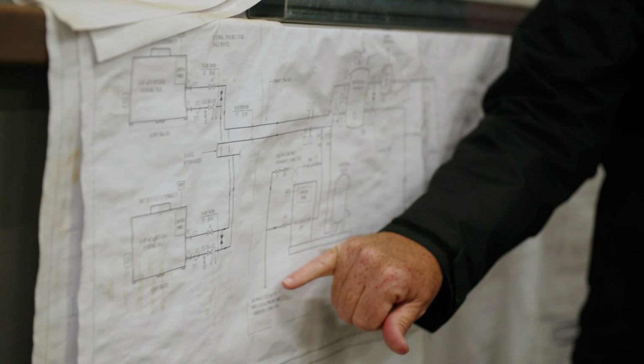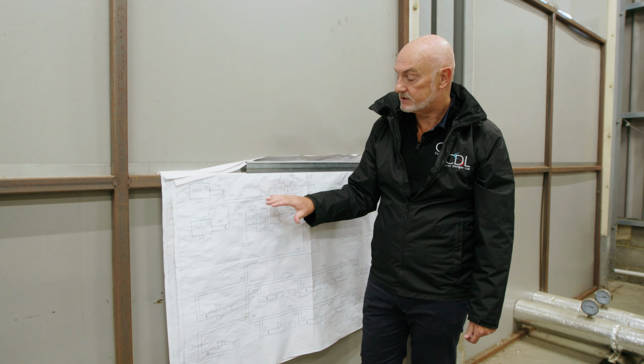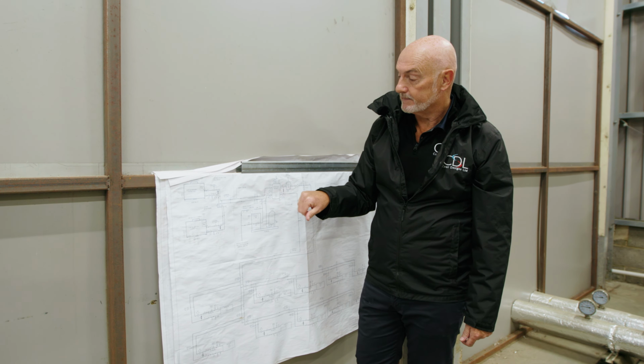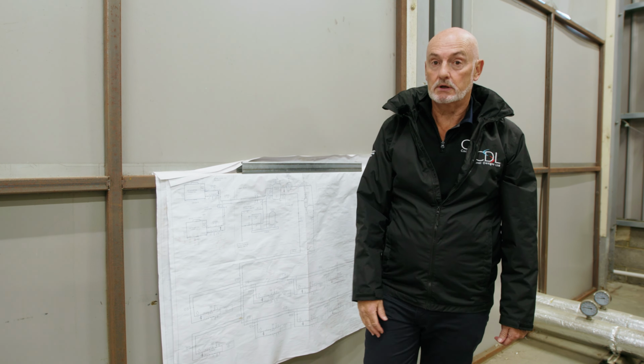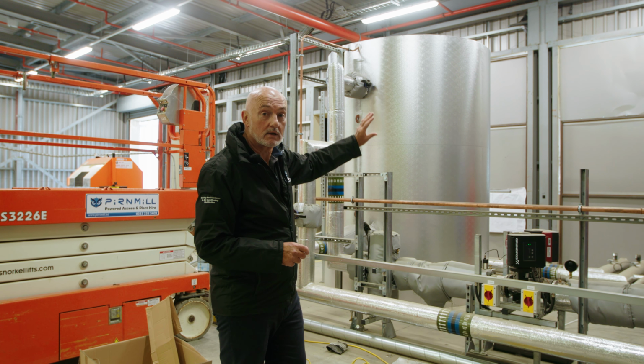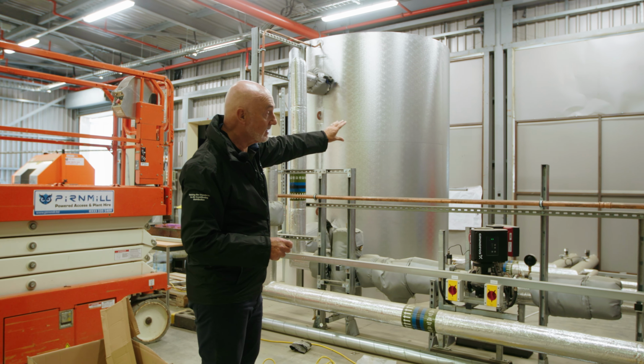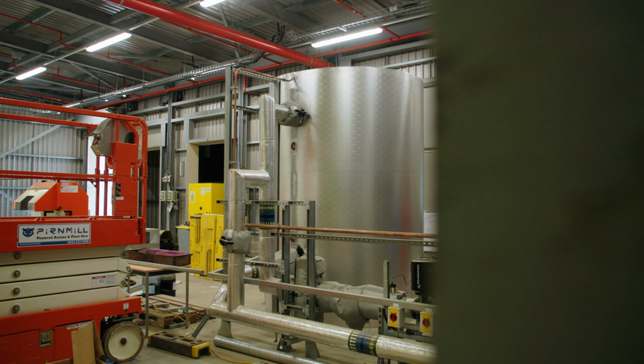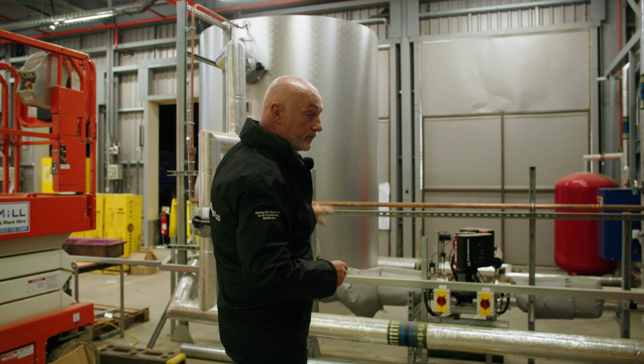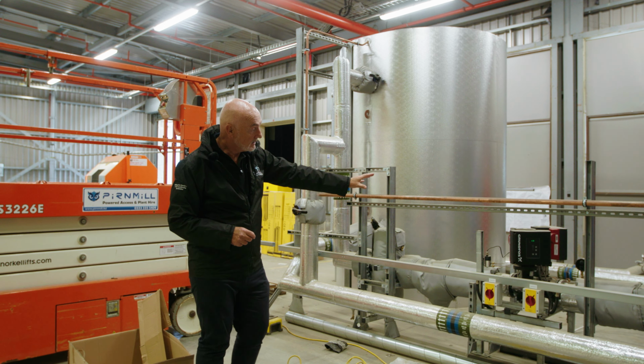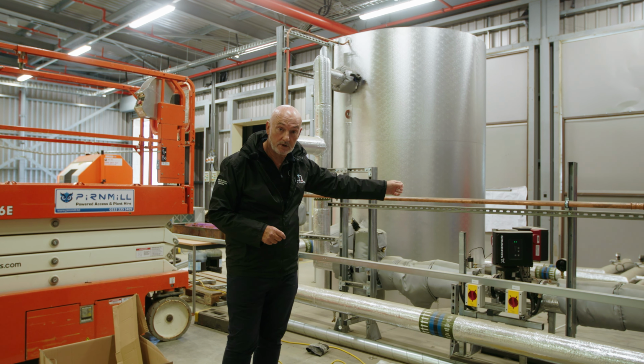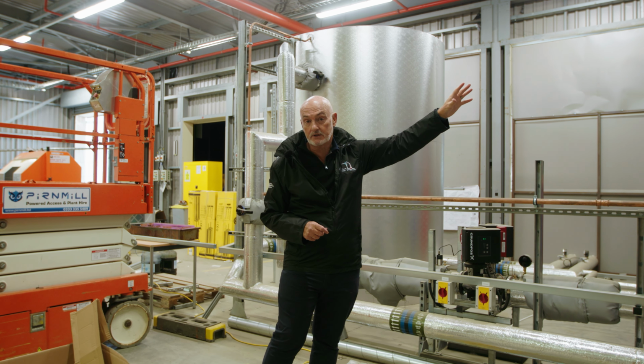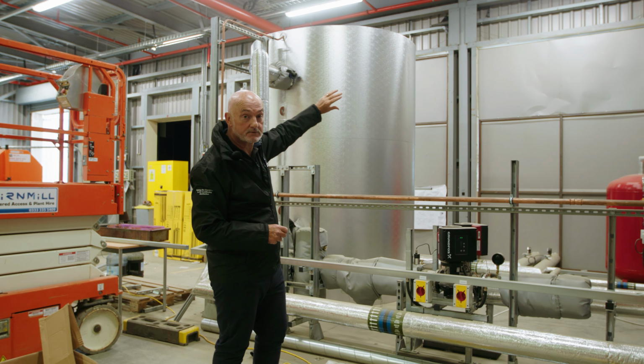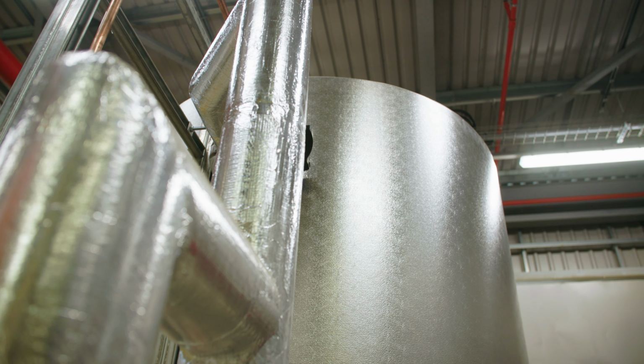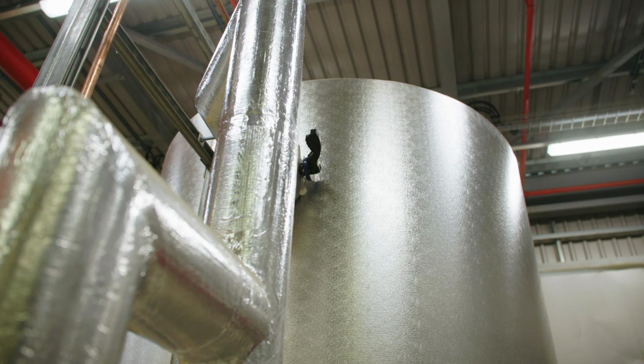This is just a little pressurization unit with some water, just to keep the system balanced, just to keep it under pressure. Whereas this is the buffer, primary circuit, secondary circuit. So beyond that panel there, we have the air source heat pumps generating the heat. The primary circuit brings us into this generously sized buffer, and this is the secondary side. From this buffer, the water is drawn by duty and standby pumps, in case one breaks down, and off and away into the warehouse. So you have air source heat pumps, primary side, generous buffer, and then secondary side, the finesse, meaning you do whatever you want with this water.